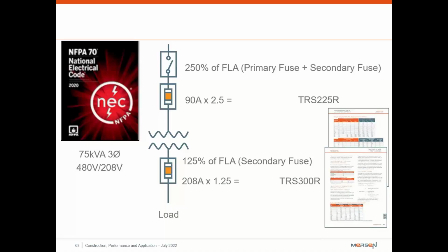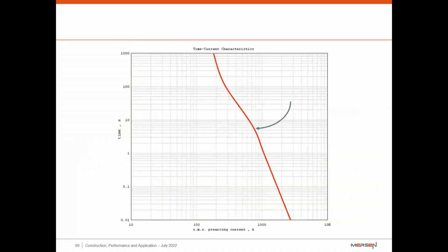So what is this actually going to look like on a time current curve? So you have your TRS225, and then you're going to have your inrush. So you can see that at 25 times for 0.01 seconds and the 12 times at 0.1 seconds, we're going to be to the right of all of that on the time current curves.